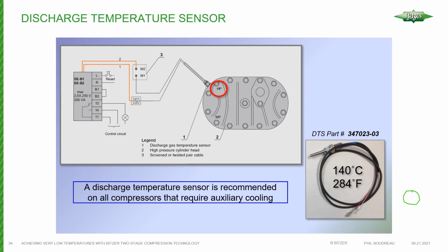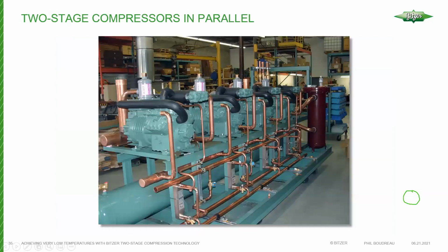Any compressor that requires auxiliary cooling, like head cooling fans, or in this case interstage cooling, in my opinion, it's always a good idea to have a discharge temperature sensor in there. It's really low cost insurance in the event that something goes wrong, where we've lost the ability to keep the compressor cool, or our discharge temperature is just too high. We can install a discharge sensor and wire it basically in series with the motor PTC sensors. Then in the event of either a motor overheating situation or a high discharge temperature, the compressor will be taken offline safely.